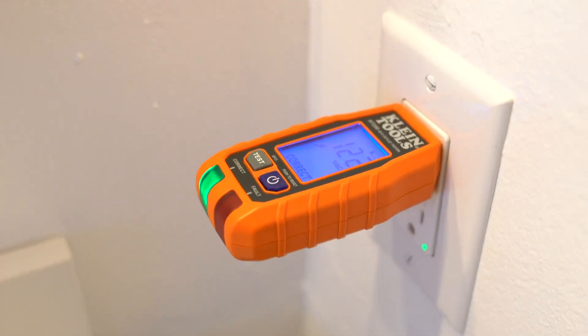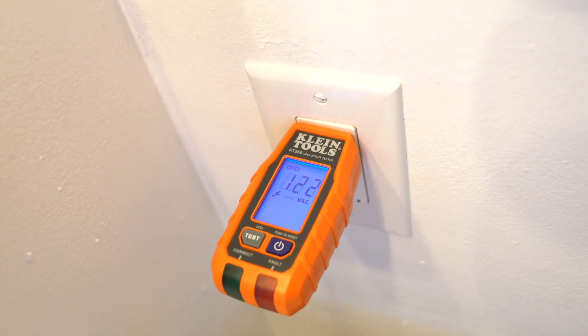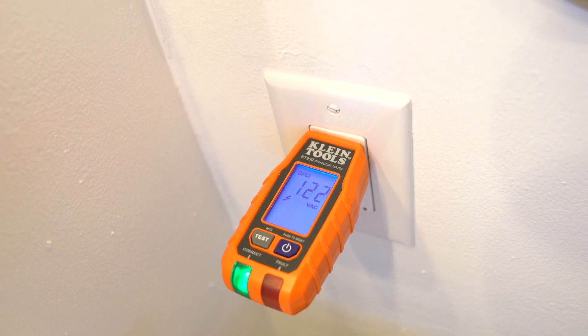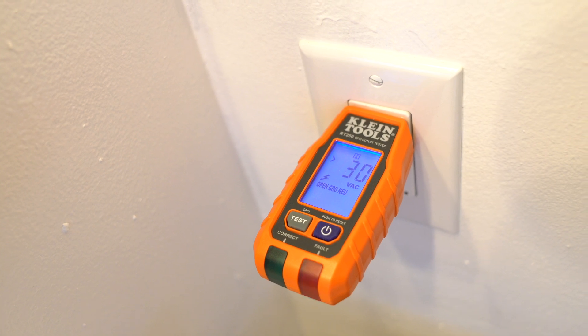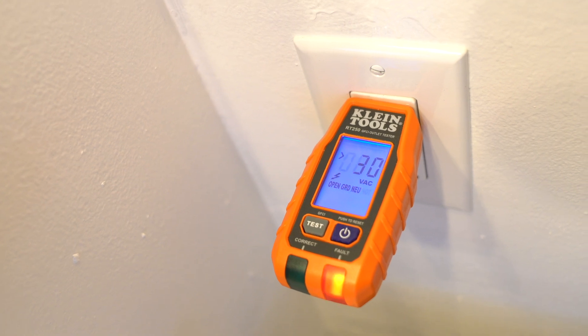After replacing a GFCI outlet, I tested it with the Klein Tools GFCI tester to make sure it works properly. However, after tripping, the display showed open ground neutral and displayed 30 volts. I reset the outlet and it showed a green light as normal. I figured out what was happening and how to address it.